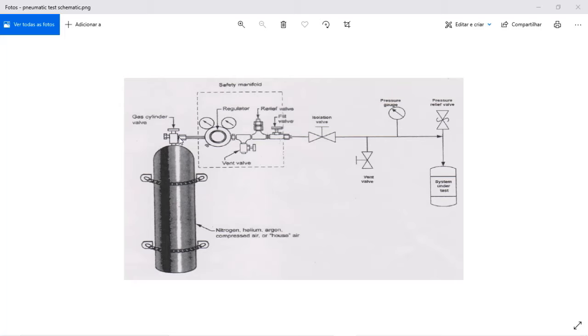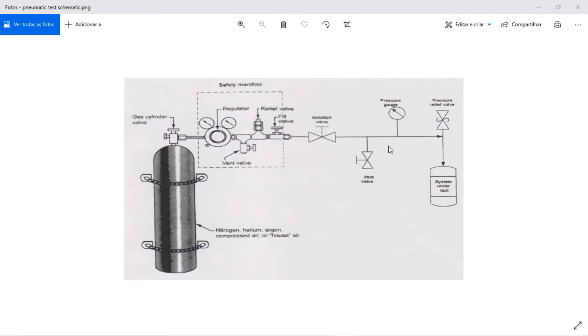And to prevent any kind of damage to the system downstream of the regulator, you always need to have a relief valve if for any reason you are able to pressurize the system downstream of the cylinder above its design pressure.